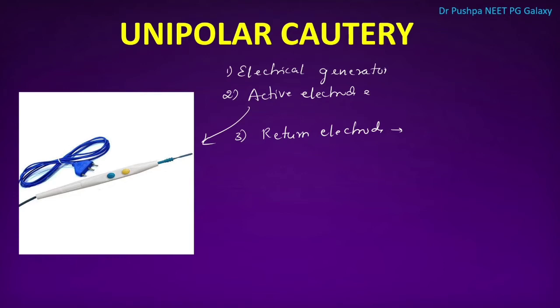In monopolar cautery, electric current passes through the active electrode, then through the patient's body, and exits from the return electrode — the cautery plate. The patient's body becomes part of the circuit. A continuous waveform gives cutting current to incise tissues, whereas an intermittent waveform gives coagulation current.